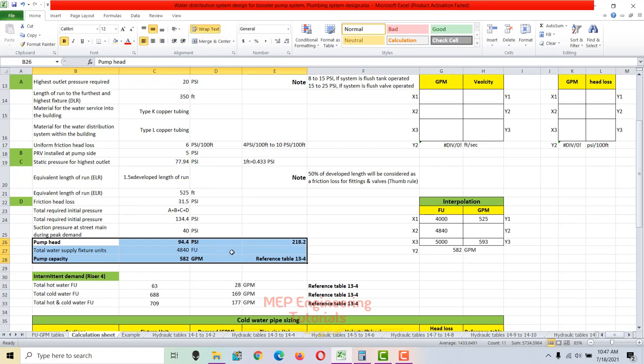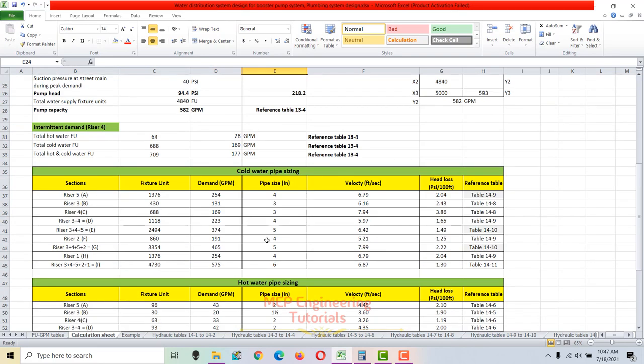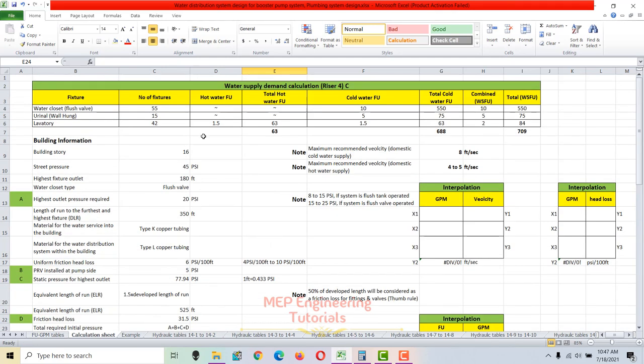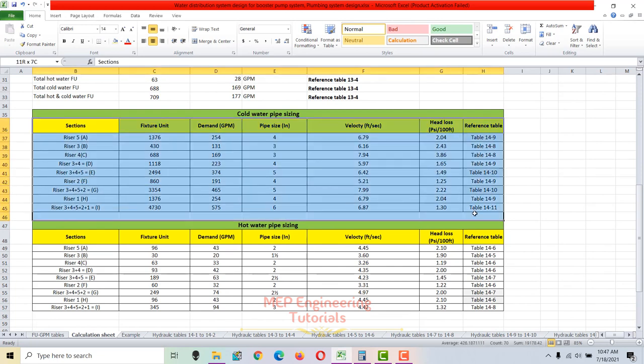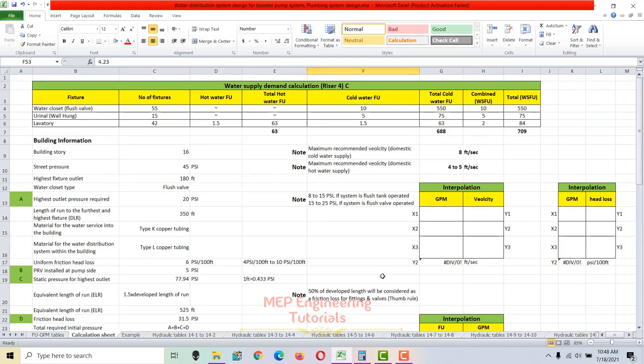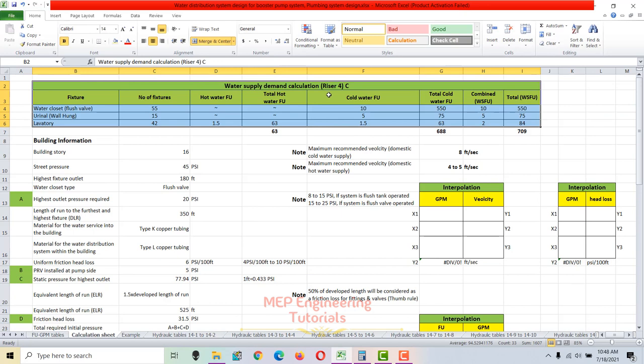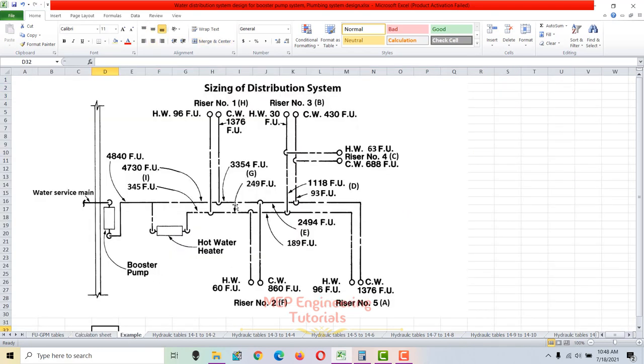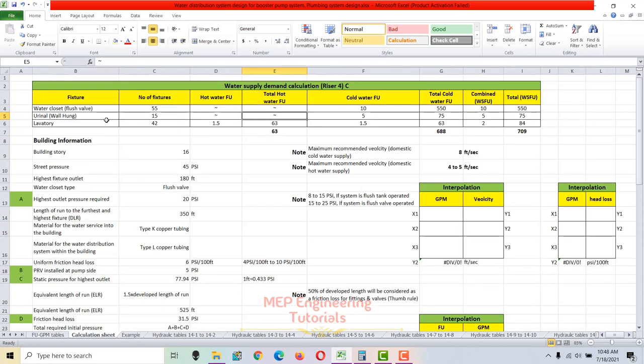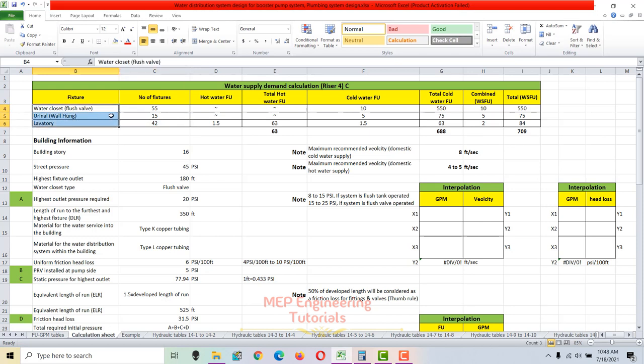Now we proceed to hot and cold water demand calculation, then pipe sizing. I'll demonstrate for riser 4, represented by section C. Riser 4 contains flush valve water closets, wall-hung urinals, and lavatories. We list all fixtures for each riser and section, then count the number of each fixture: 55 water closets, 15 urinals, and 42 lavatories.